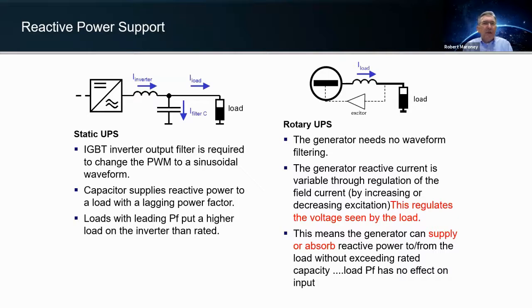So, reactive power support. With a static UPS, you use the IGBT inverters with an output filter to change the PWM to sinusoidal. Essentially the capacitors are, again, that smoothing waveform, and they also work with lagging power factor. When you use a rotating machine, and we'll get into details of how it actually works, there's no need for the waveform filters, for one. The generator provides reactive current to the system as needed based on excitation from the output of the system. This regulates voltage as seen by the load. And this means that the motor generators not only can supply but also absorb reactive power based on the needs of the output power form.